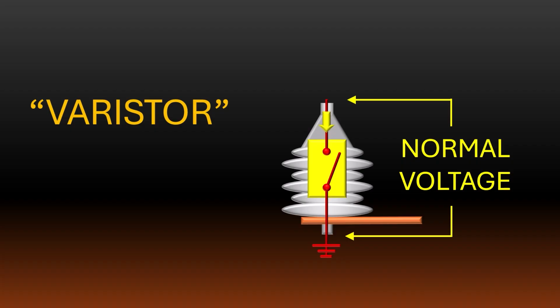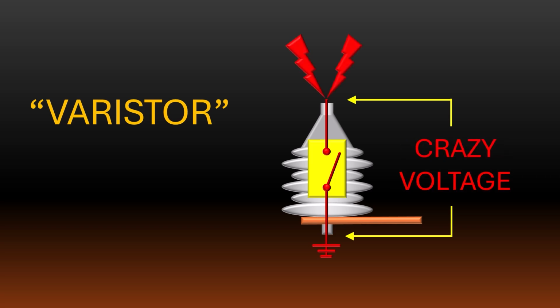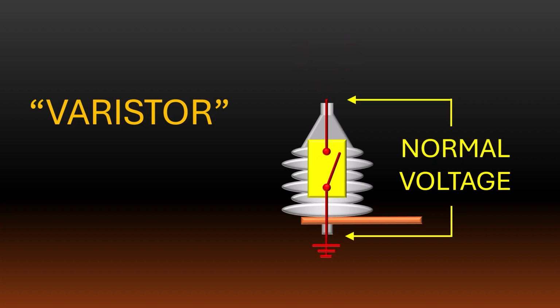However, when a lightning strike hits one of the phase conductors, crazy high voltages of hundreds of millions of volts can travel through the conductors. This energy needs to be offloaded from the system before it can cause any damage or injury. When this happens, the varistor senses the extremely high voltage and instantly acts like a closed switch and lets the energy pass through to ground. When the voltage returns to normal, it instantly returns to its open switch state.